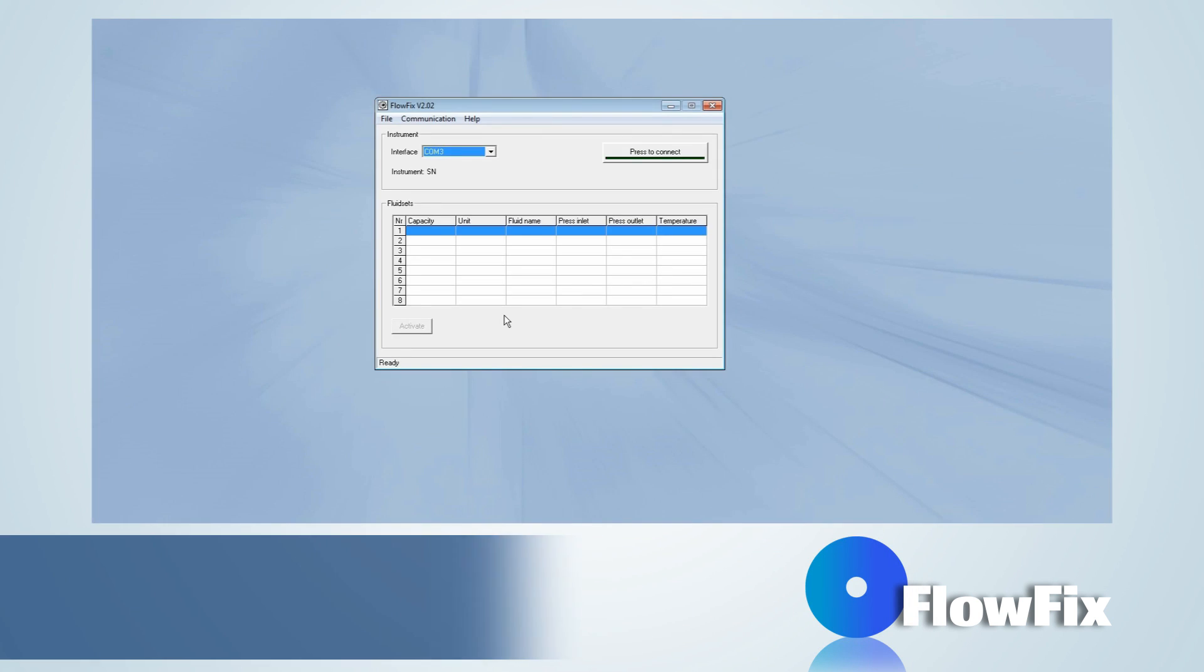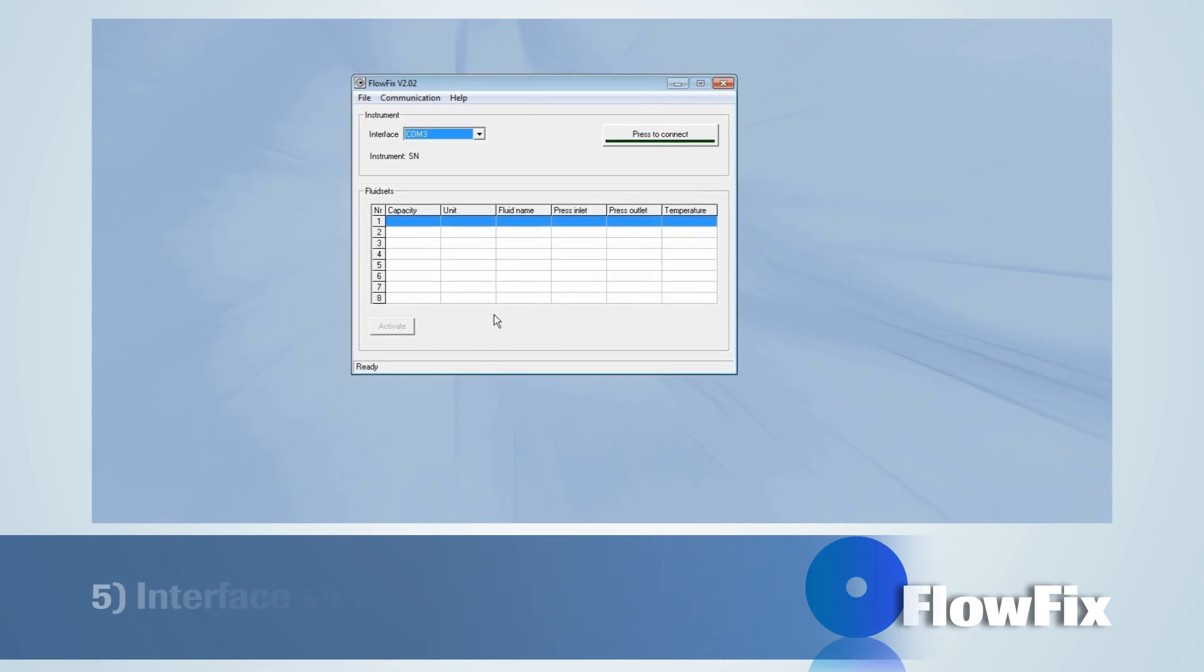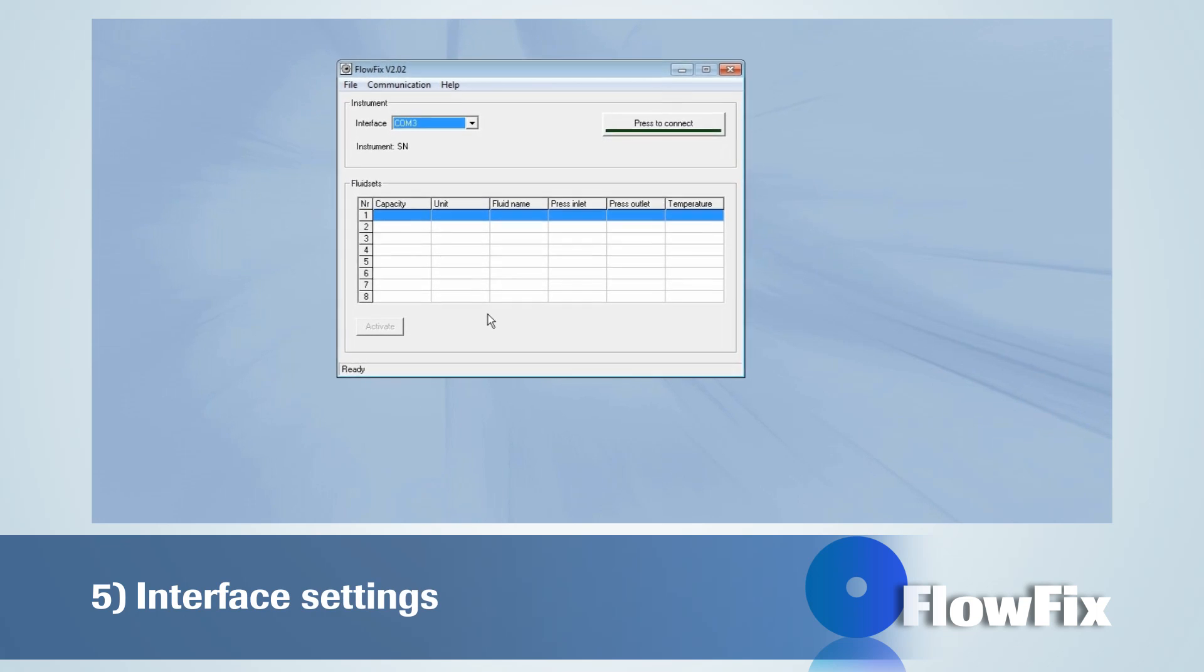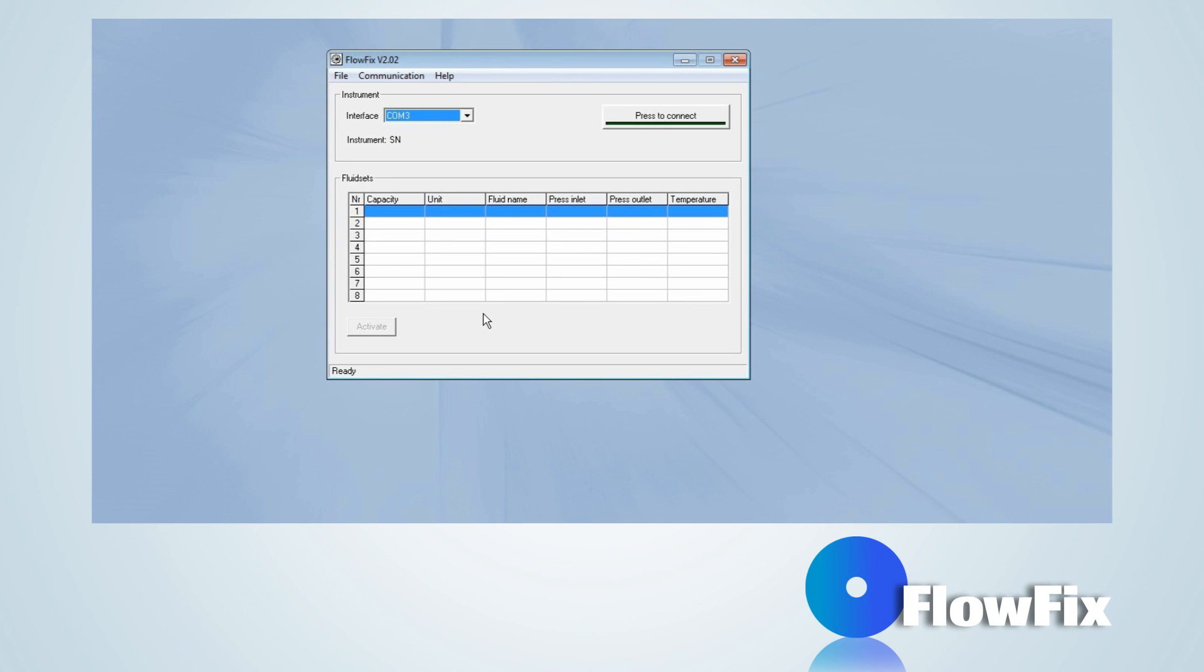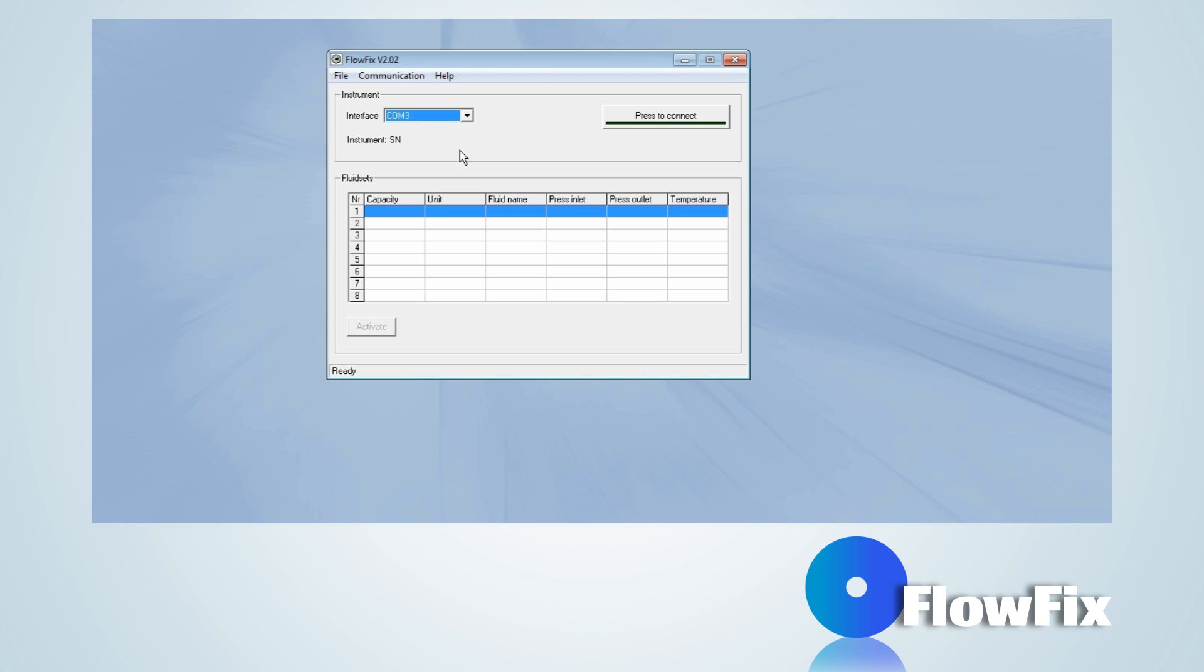Before communication with the instrument can be established, the interface settings have to be configured correctly. At Interface, the COM port can be selected. The program only supports an RS-232 baud rate of 38,400 baud.